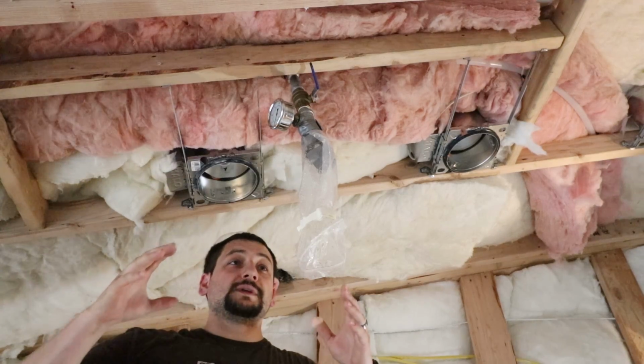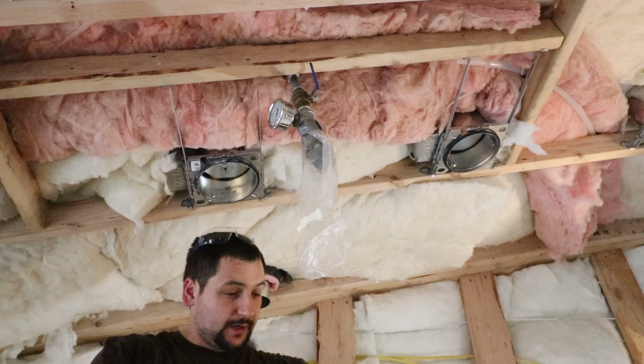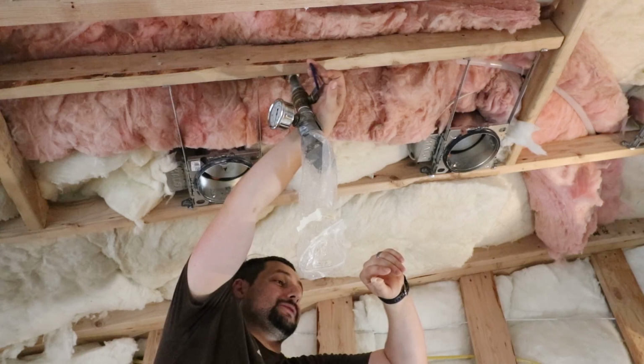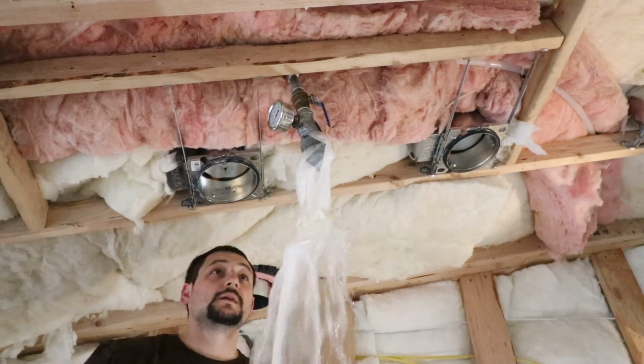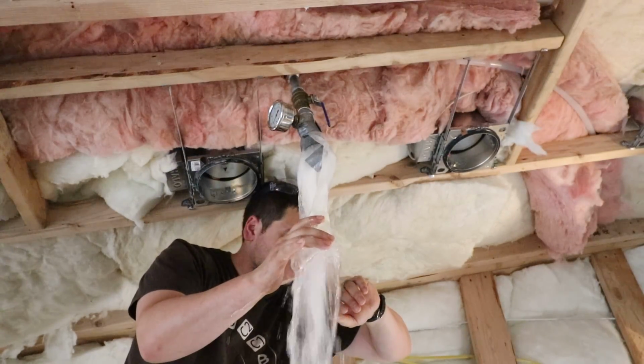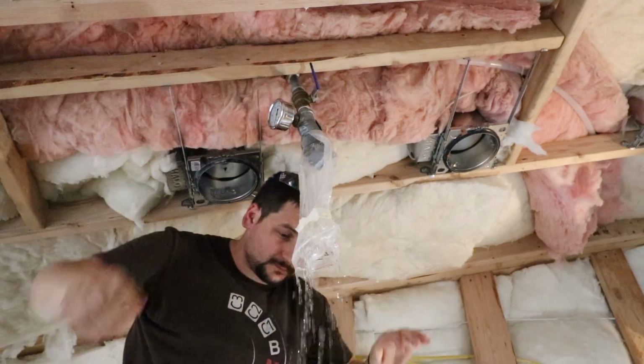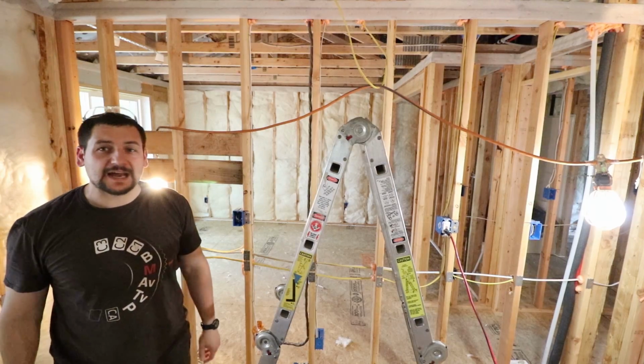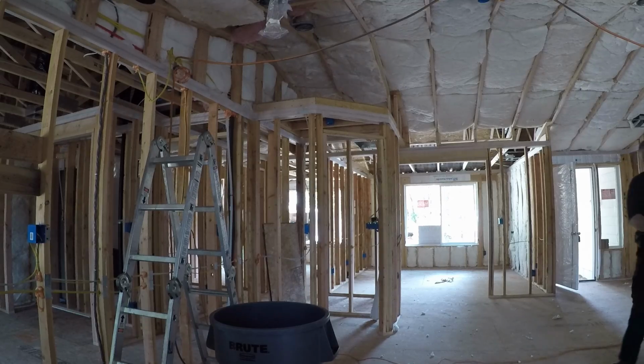All right, I've got you guys zoomed in here. I put a little bit of tape around this thing, and I'm going to time it this time. I'm going to run it for, we'll say, a minute, to make sure we're within spec. All right, that was 1 minute. So we're at 13 gallons in 1 minute. That's well within spec.